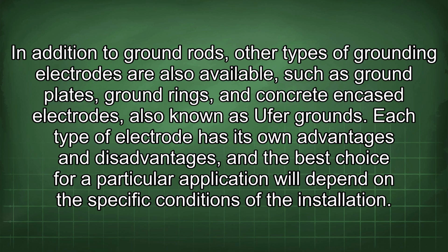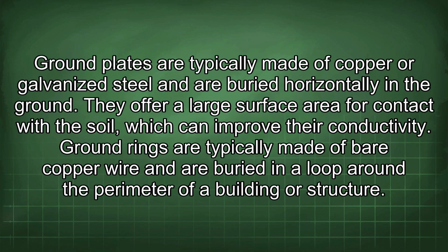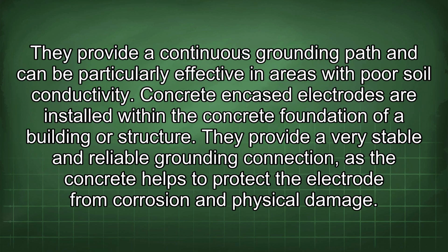Each type of electrode has its own advantages and disadvantages, and the best choice for a particular application will depend on the specific conditions of the installation. Ground plates are typically made of copper or galvanized steel and are buried horizontally in the ground. They offer a large surface area for contact with the soil, which can improve their conductivity. Ground rings are typically made of bare copper wire and are buried in a loop around the perimeter of a building or structure. They provide a continuous grounding path and can be particularly effective in areas with poor soil conductivity.